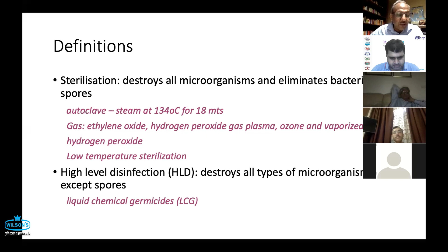So with this background, what are the basic steps to clean and perform high level disinfection? Please note here that first thing starts in the endoscopy room, and then you go to the disinfection room, and there the most important things are the two, that is the manual cleaning and the seventh point, the drying. Because these particular steps, rinsing, high level disinfection, and again rinsing, all these now in the automatic processes come automatically. But the manual cleaning is totally individual human dependent.